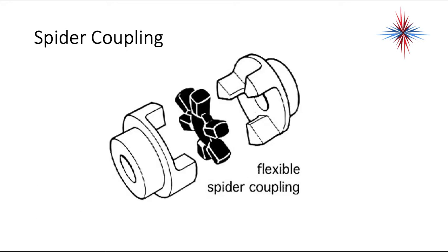A spider coupling is a flexible coupling that allows, if for some reason it seizes up, it allows the motor to be disconnected. Your motor would be mounted here, your blower wheel would be mounted here, and there's a flexible coupling in here that helps with vibration. If something fails or seizes up, you're not going to burn out a motor.